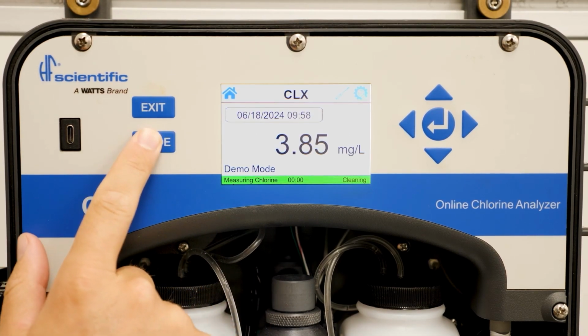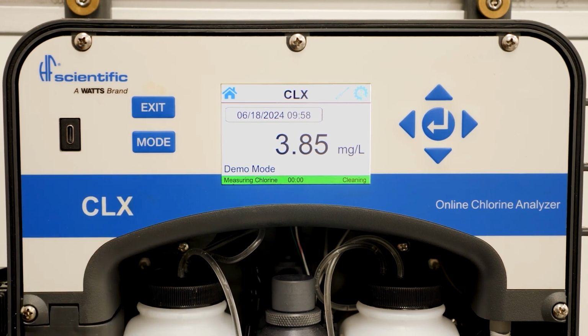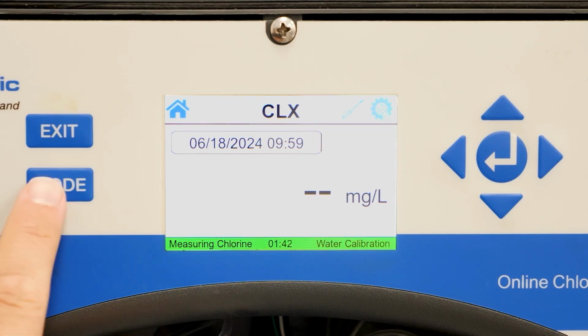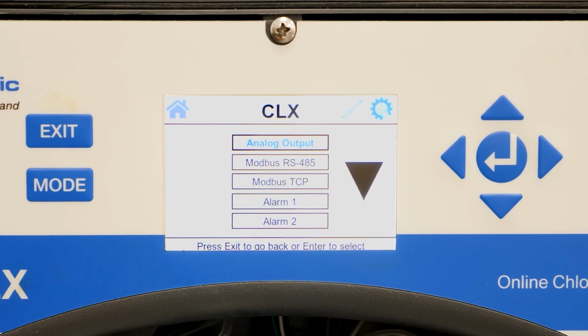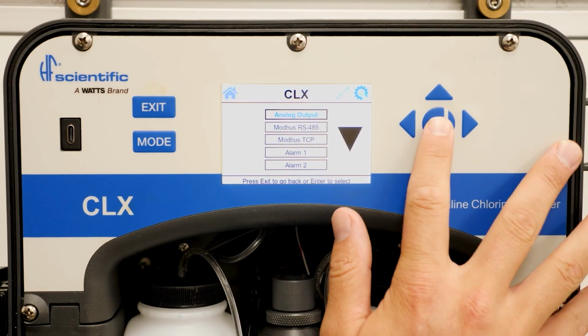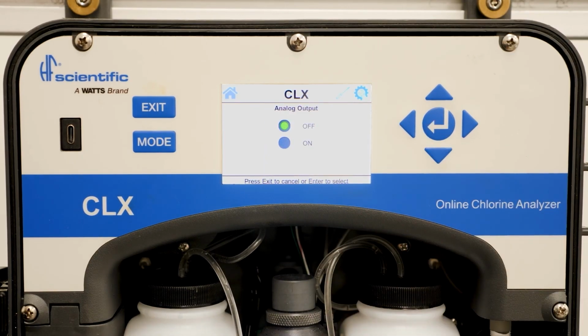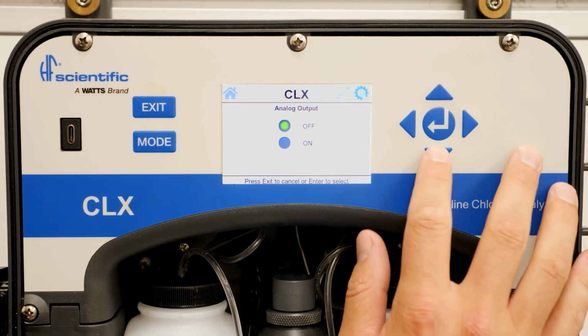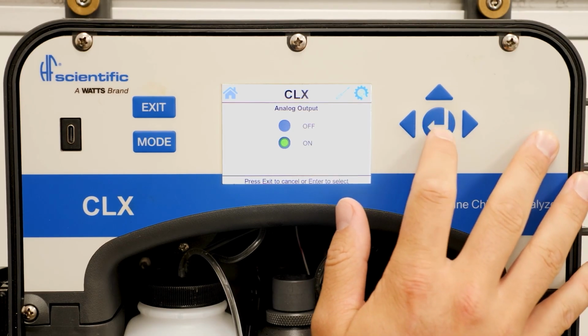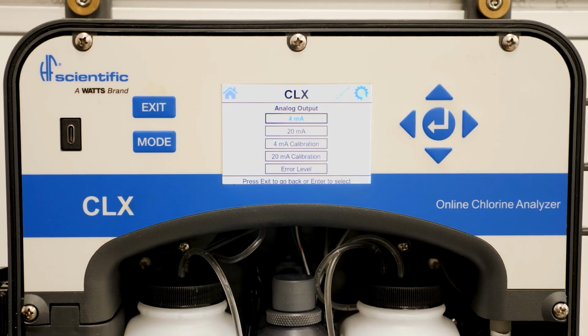The configuration menu has also been updated on the newest version of the CLX. By hitting Mode twice from the home screen, you will be presented with all the options in the configuration menu. Analog output allows you to toggle the 4 to 20 signals on and off.